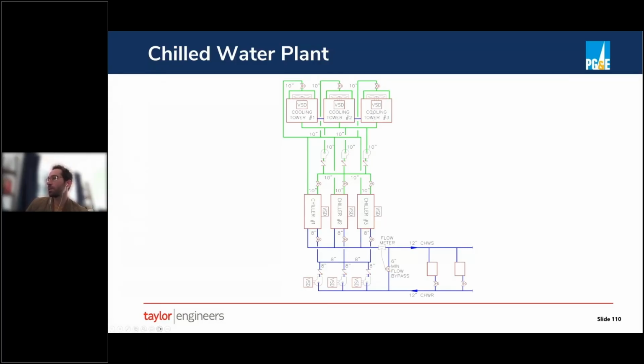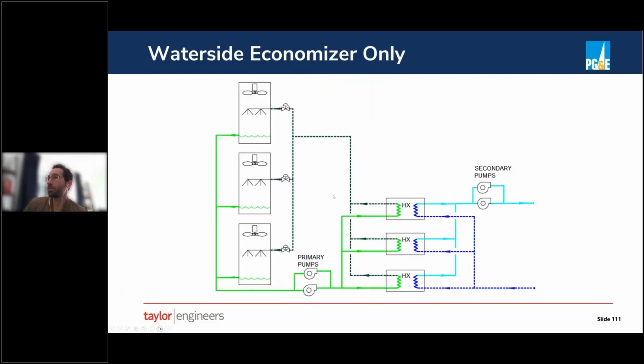The same thing is likely to be the case for both the chilled water pumps and the condenser water pumps. And we'd probably be doing exactly the same thing with the cooling towers as well. The next system option is what we'll call a waterside economizer only system. So we basically have deleted the chillers entirely here. And what you're seeing is that we have an open condenser water loop that's flowing through the cooling towers.